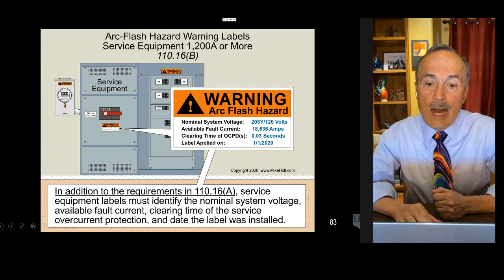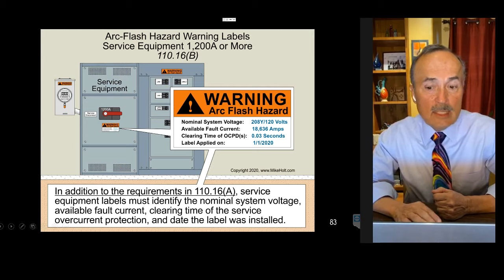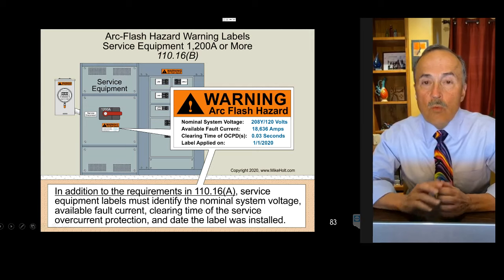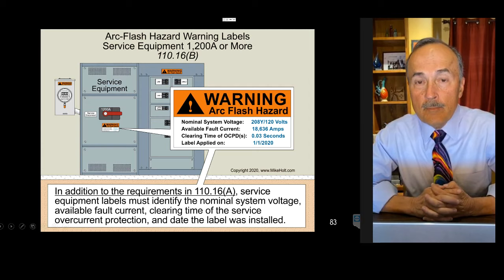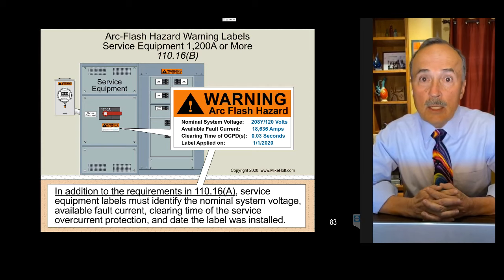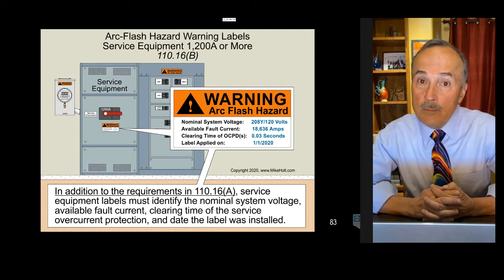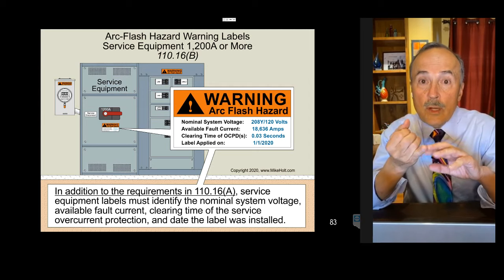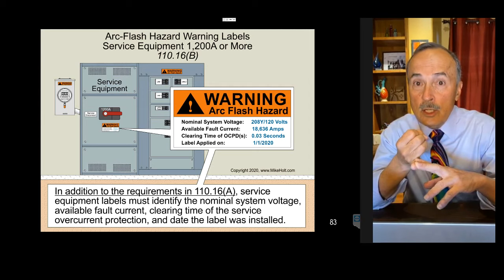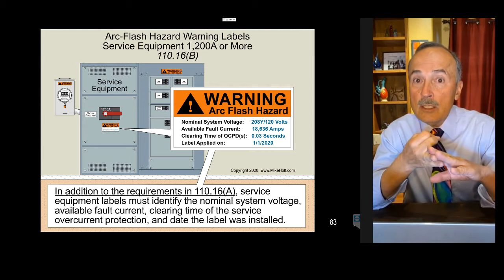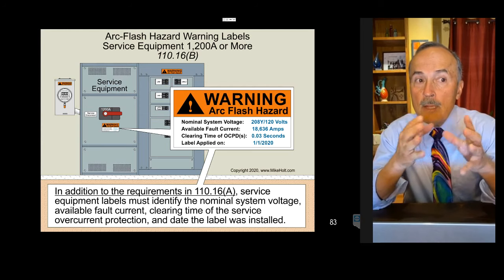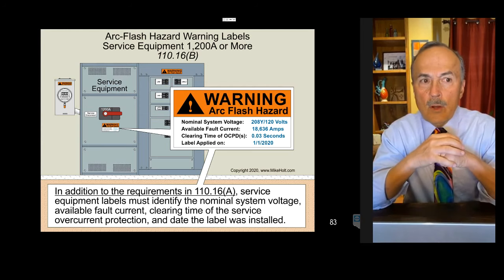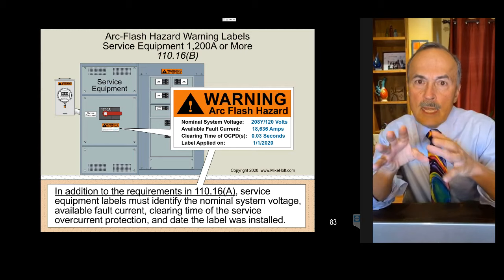110.16(B) in the code says, hey, listen, as the heading says, if you have a service of 1200 amperes or more, we need a label. Now, here's what we want on that label. We want to know the voltage. We want to know the available fault. And we want to know how long is it going to take for that protective device to clear. And we want to know what day did you put that label on there. You're thinking, how the heck am I going to get that information? Well, you need to know what you're doing. I mean, you're supposed to be the expert.